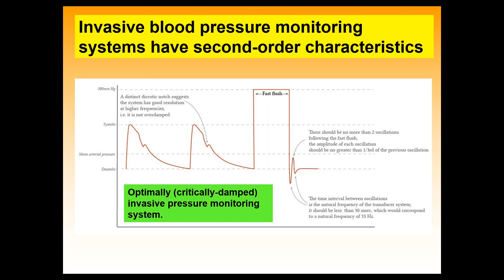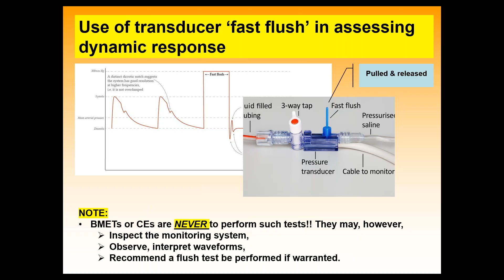Do you guys see these yet? Is this stuff still out there in your transducers if you look at it? Okay. Biomed guys, you never want to be the one to do that. You can get yourself in some really hot water, because you're effectively administering a bolus of heparinized saline. So only the clinicians should do that. You can suggest that they do it if you strongly suspect that this system has some issues associated with it. You can have them do that fast flush test, because I don't know how often the nurses are trained to really understand what it is they're trying to do when they do that particular test. But you can definitely recommend that it be done, and you can then qualitatively use that information to potentially troubleshoot a faulty system.